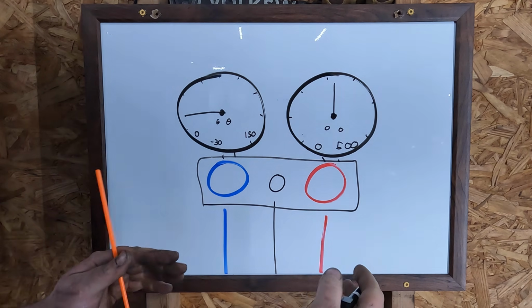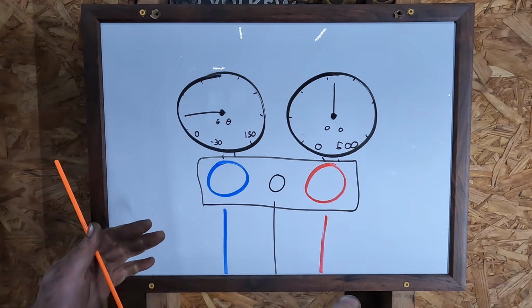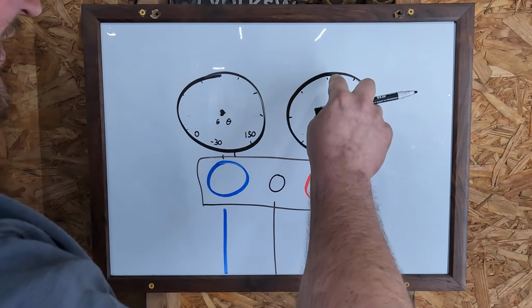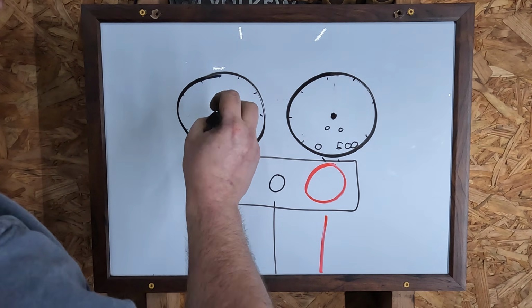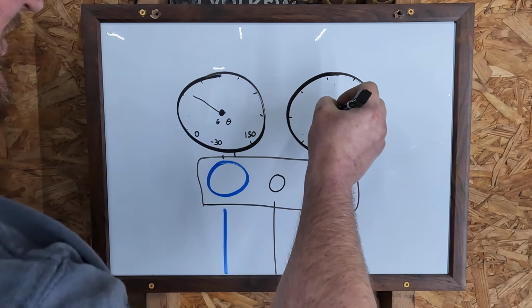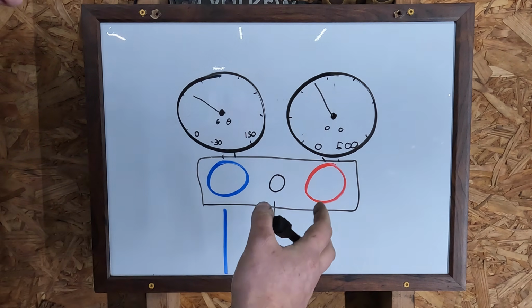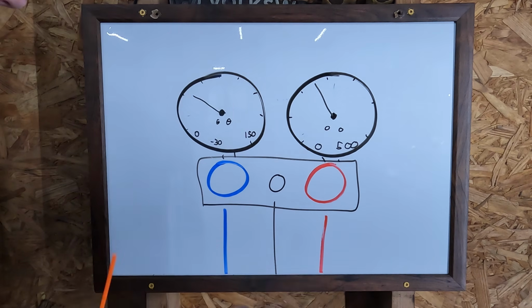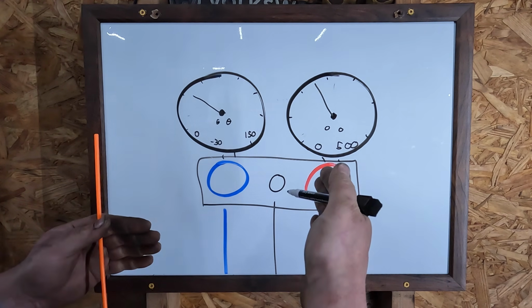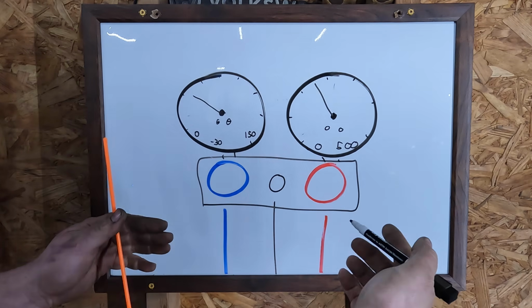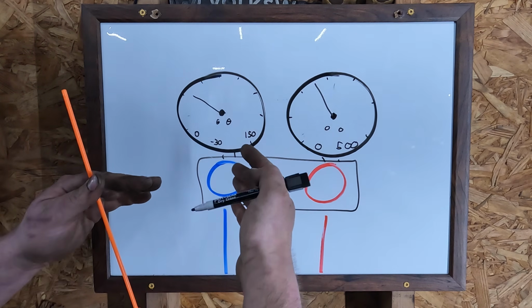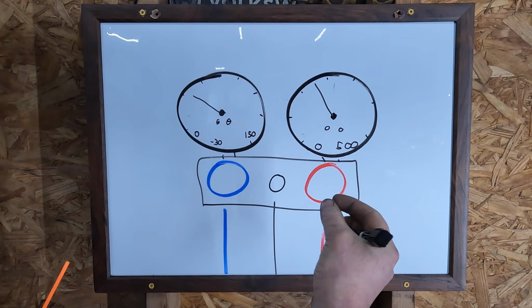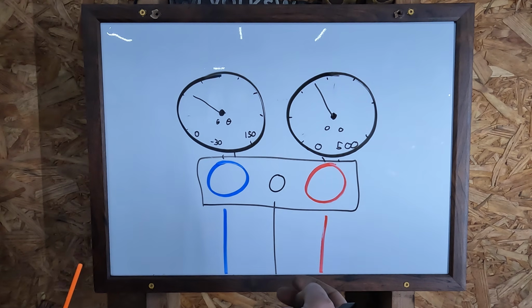Now, once you've ruled out electrical problems and the compressor is kicking on, but it's still not cooling, by far the most common problem is just a weak compressor. With that said, the closer those two numbers are, the weaker the compressor. So if it's not building suction on one side, your low side's going to be high, and if it's not building pressure on the other, your high side is going to be low. And that's what a weak compressor will look like. Unfortunately, however, if you have an expansion valve that is hung open, it could also look something like this, but that is far less likely because the expansion valve doesn't actually have metal bits flying around in it.